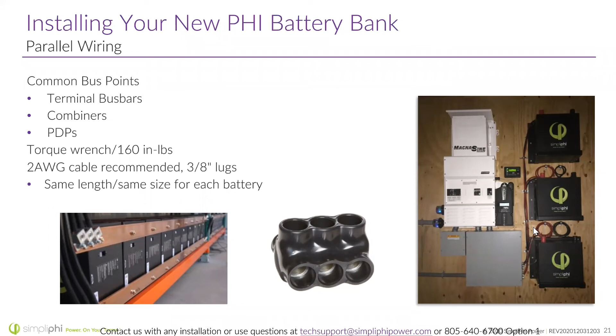As far as commissioning your new batteries, be sure to connect all batteries in parallel on the same bus, turn them all on before connecting them to the charging device. Remember, if you turn on just one battery and it's already connected to the charge controller, that charge controller or inverter might have a startup surge current that's too much for one battery to handle. So it's always recommended to have some sort of DC disconnect beyond the battery bank.